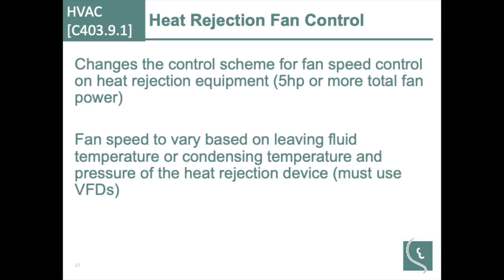Heat rejection and fan controls, noting there's a specific requirement for how to do that now, noting the leaving fluid or condensing temperature and pressure. So again, more and more VFDs, but providing more guidance as far as how to get the controls right.